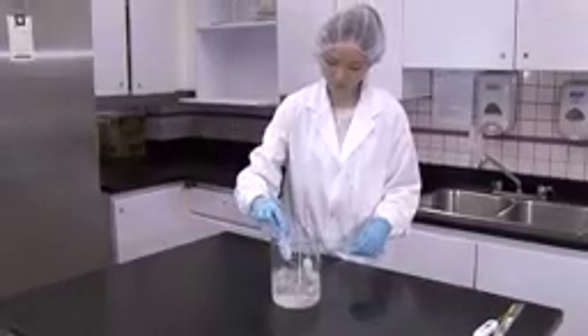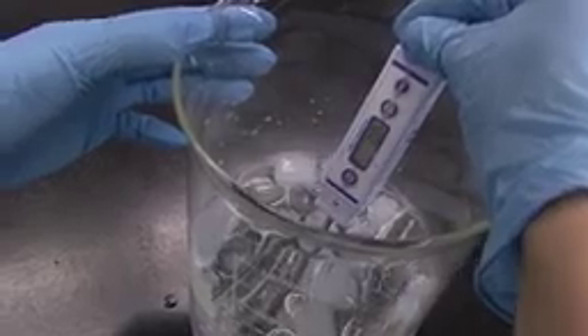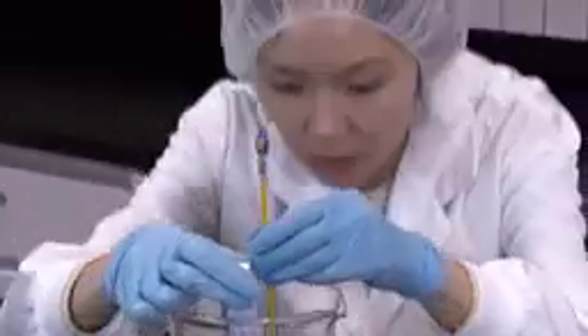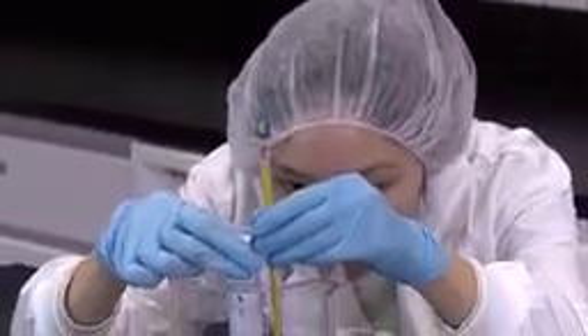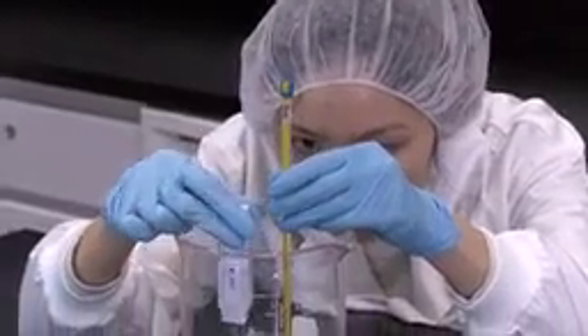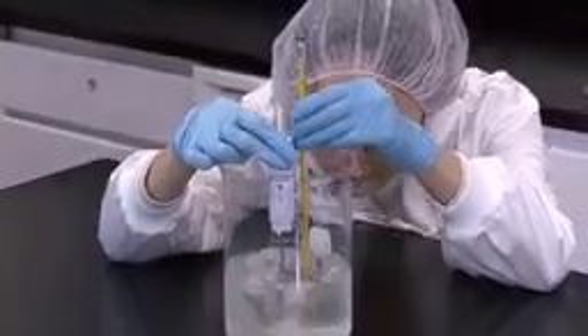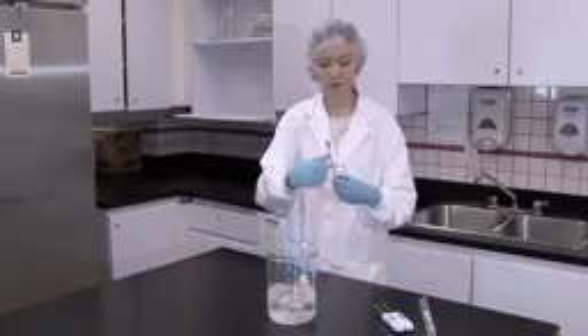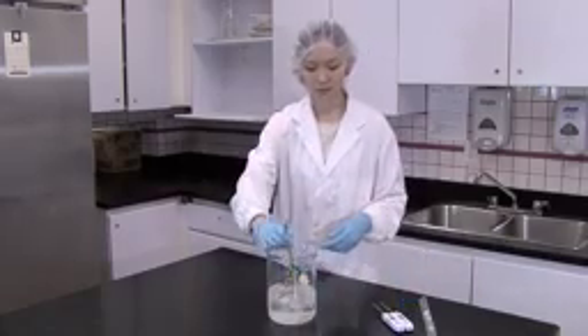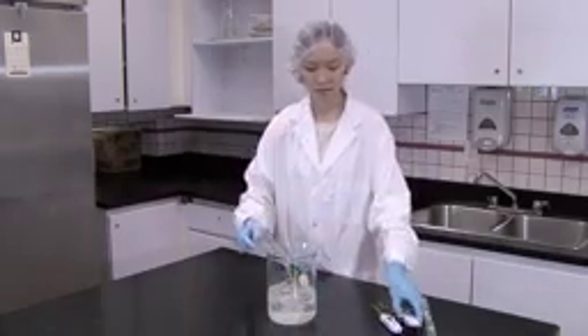To determine if your thermometer is reading the freezing temperature correctly, you need to add some ice to cold water and allow it to equilibrate. Ensure that there is some ice remaining in the ice bath and insert the thermometer so that the end does not touch any ice. If corrections are required, you'll just need to follow the instructions that should have come with your thermometer.